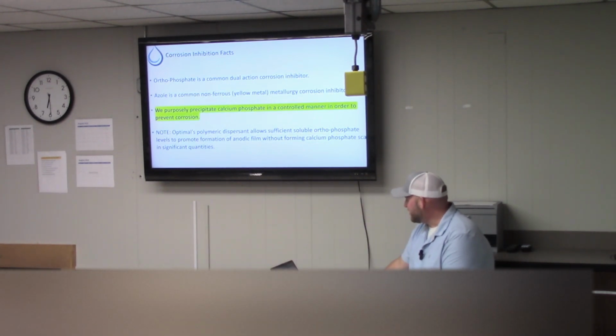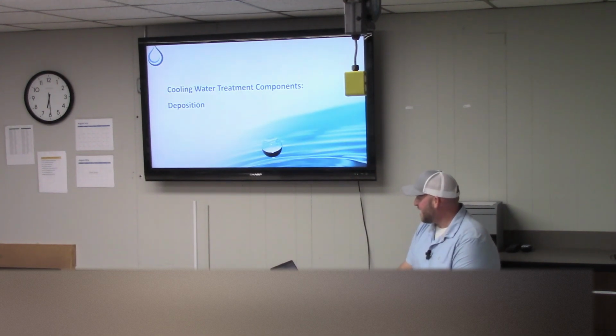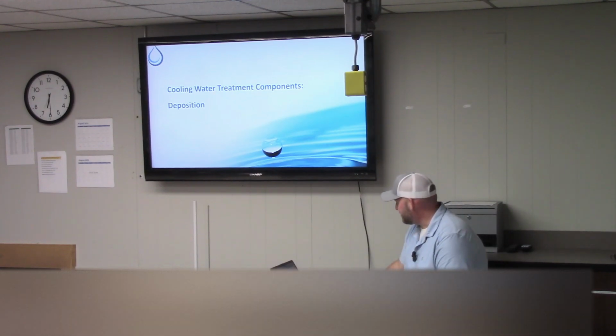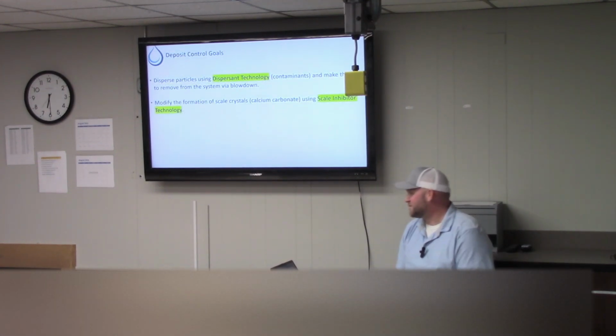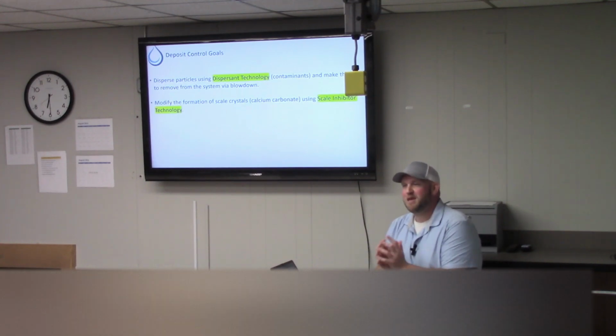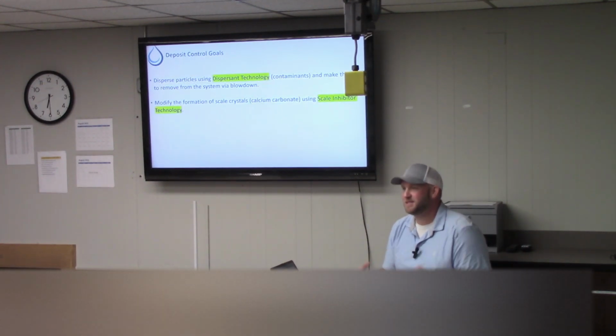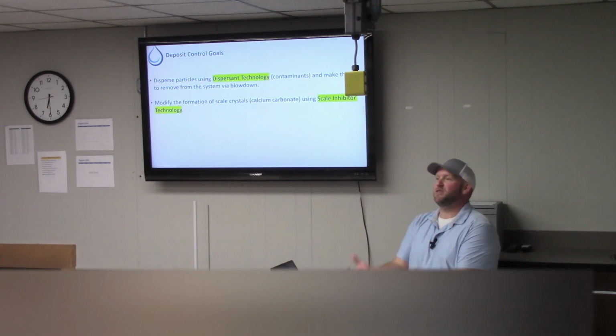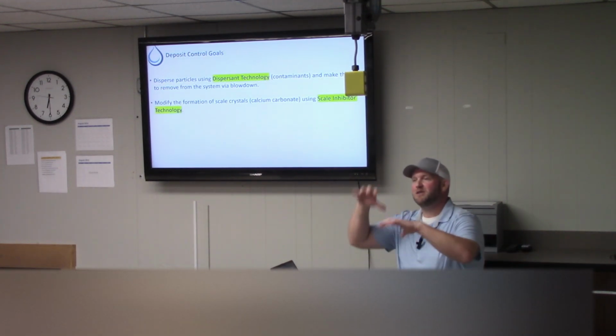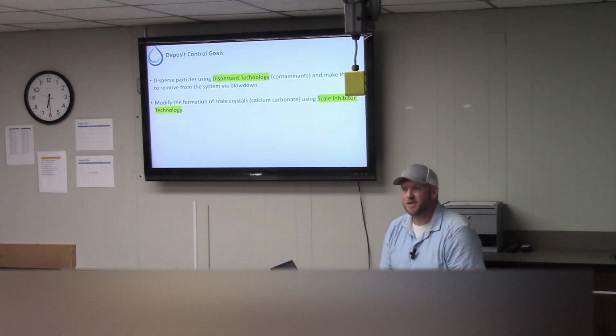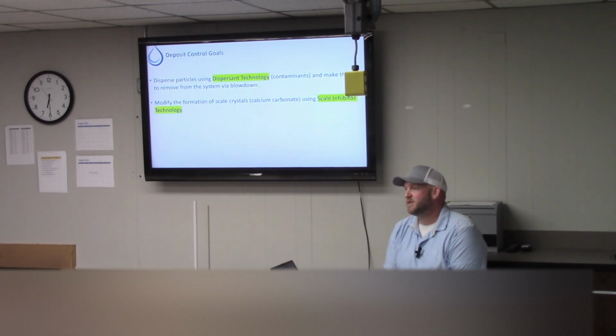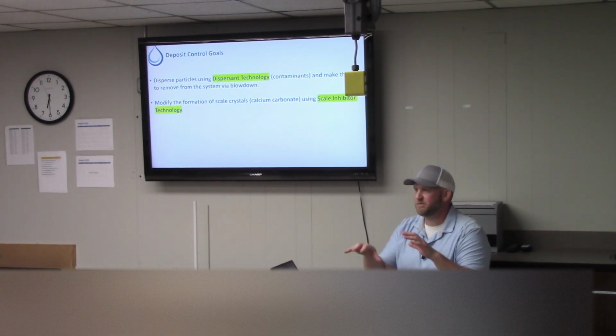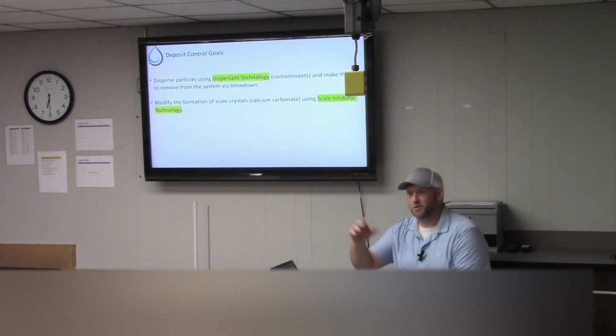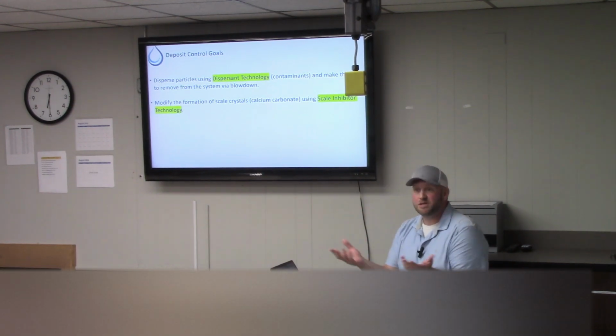Okay, I do want to go ahead and touch on deposition now as we finish the last 9 slides. If we look at this, for example, deposition control, we use dispersants. We have one main chemistry that we typically feed that has all these actives in it. We proportion it so that as you cycle up the towers, the right amounts of each one are in your specific system. We've made our blends to match this local area's water, and thanks to those concentrations, there's a bit of wiggle room we can do from summer to winter should the water change a bit, which it does in the river.